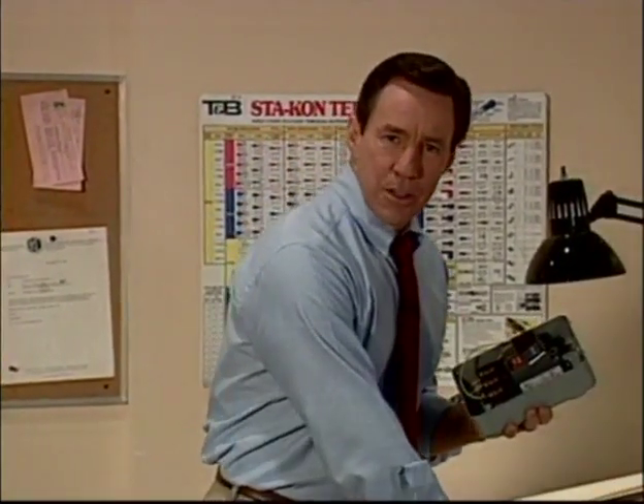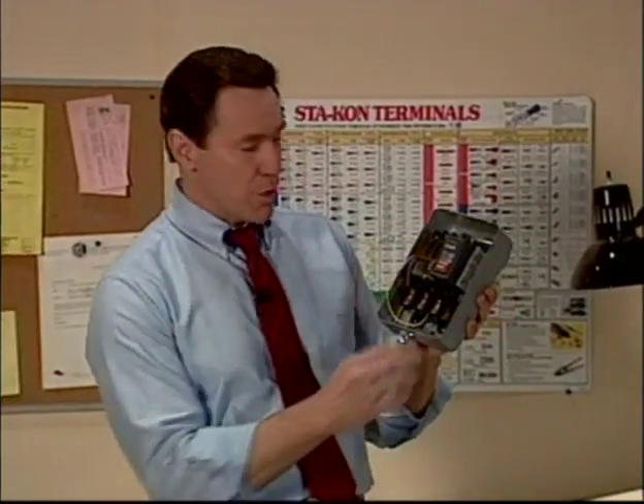The manual motor starter functions like a switch which will connect the power lines to the motor by the activation of the switch, which closes the contact. The magnetic starter functions like the magnetic contactor, which uses a coil to activate the contacts. Both classes of starter have overload protection for the motor. A little later in this module, we are going to cover more on overloads in detail, but here we're going to go over their responsibility in a starter, which forms part of a motor control circuit.